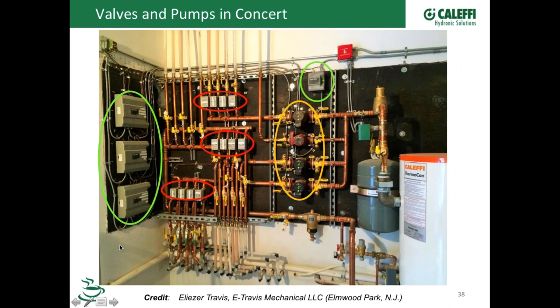Yep. I think we show some examples of that in a couple of our different hydronics schematics, where the question is whether to put the pump before the buffer tank and the hydraulic separator. In that case, you could have a pump dedicated to the indirect heater that goes right from the boiler to the indirect. And you could prioritize that too, right, Cody? If you wired it that way, sure. If you want everything to shut off while it's recovering that domestic water load, you could prioritize that. Our relays make it easy to do that. We've got one relay that says right on it, priority pump, that you can use to lock everything else out until you recover that load.